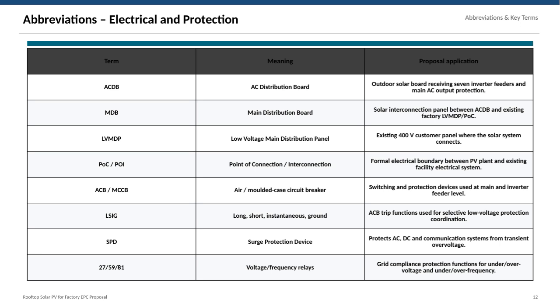The SPD, or surge protection device, safeguards the AC, DC, and communication systems from transient overvoltages. Finally, relays labeled 27, 59, and 81 provide grid compliance protection by monitoring for under and over voltage, as well as under and over frequency conditions. Understanding these terms ensures clear communication and effective implementation of the solar PV system.